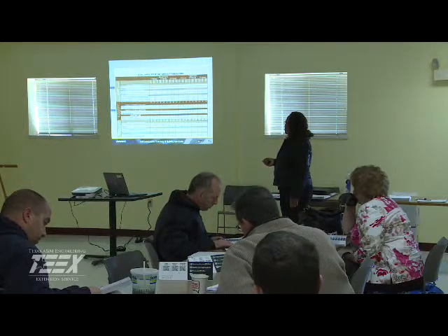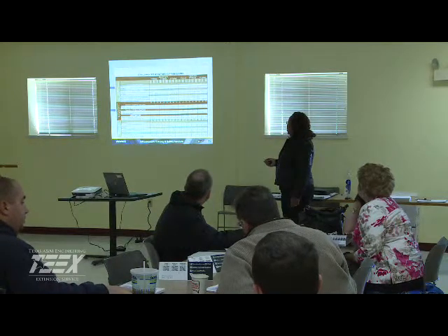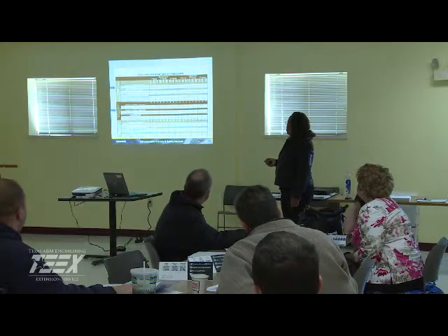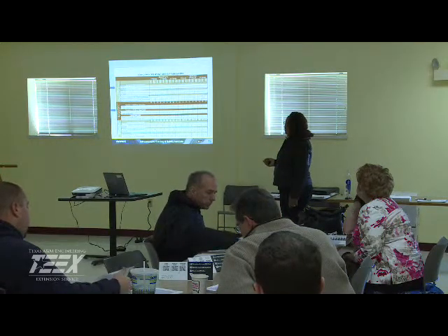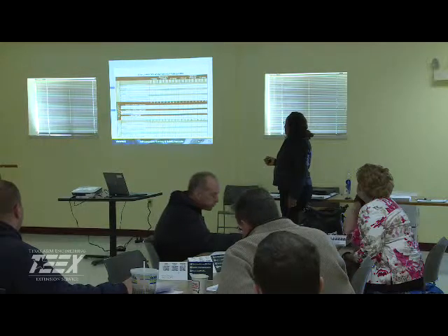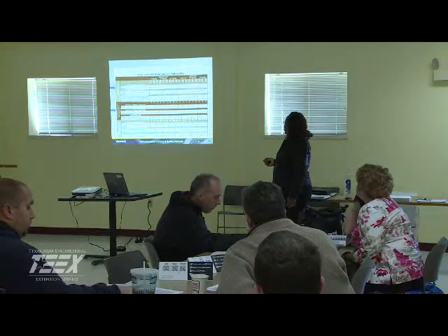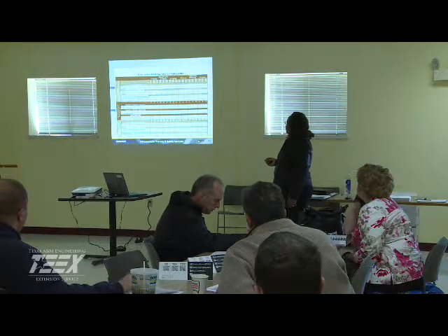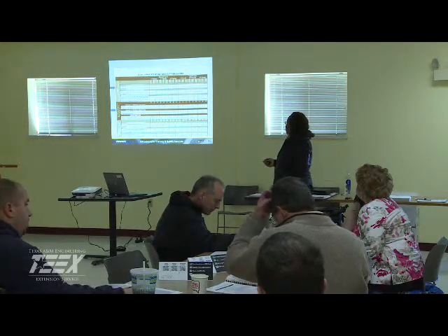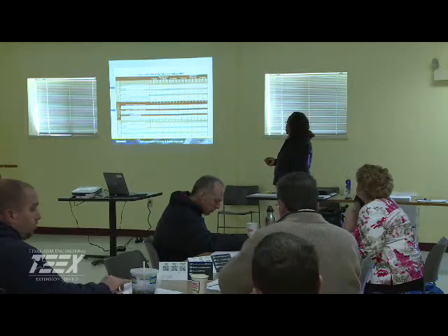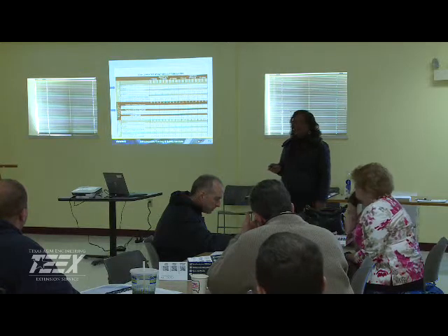All right, and I know you can't really see this, but again, I'll give you the website where you can go and look at it. For the inorganic contaminants, small systems, if you have a waiver, then you're looking at the 2nd cycle. You need to pull at least 1 sample within that 9-year period, 1 in the 2nd and 1 with the 3rd. If you have no waiver, you're doing IOCs every 3 years.